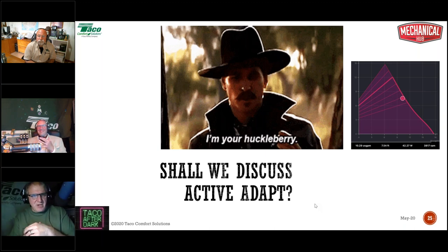All right. So what is the effect of outdoor reset on delta T, asked Robert O'Brien? Virtually none. It doesn't care what the water temperature is. People say, oh, they're going to fight together. No, they don't fight together. It's a pump, for goodness sake. It's a very benign, non-aggressive, peace-loving, conscientious objector type pump. It doesn't want to fight with anybody. All it wants to do is check what the water temperature is going out and send water back to the boiler a prescribed amount lower, typically 20. There's no fighting involved. I don't know where that stuff comes from.